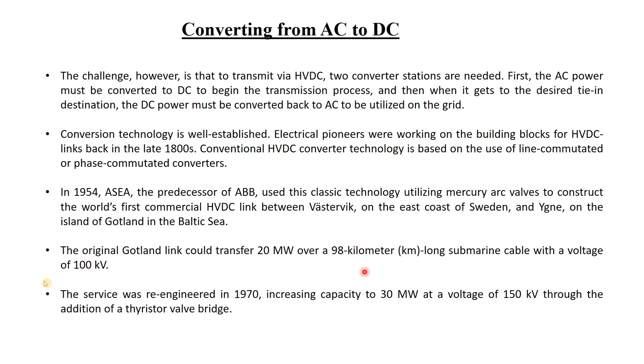If you want to increase the power transmission, you have to increase the voltage, because voltage times current gives you the apparent power, and cos phi is there depending on the load. Then to maintain the same current, because the conductor has some current carrying capability, you cannot suddenly replace the conductor. If the conductor has the capability of a certain ampere, you cannot increase it. That is why increasing the voltage is much more convenient.